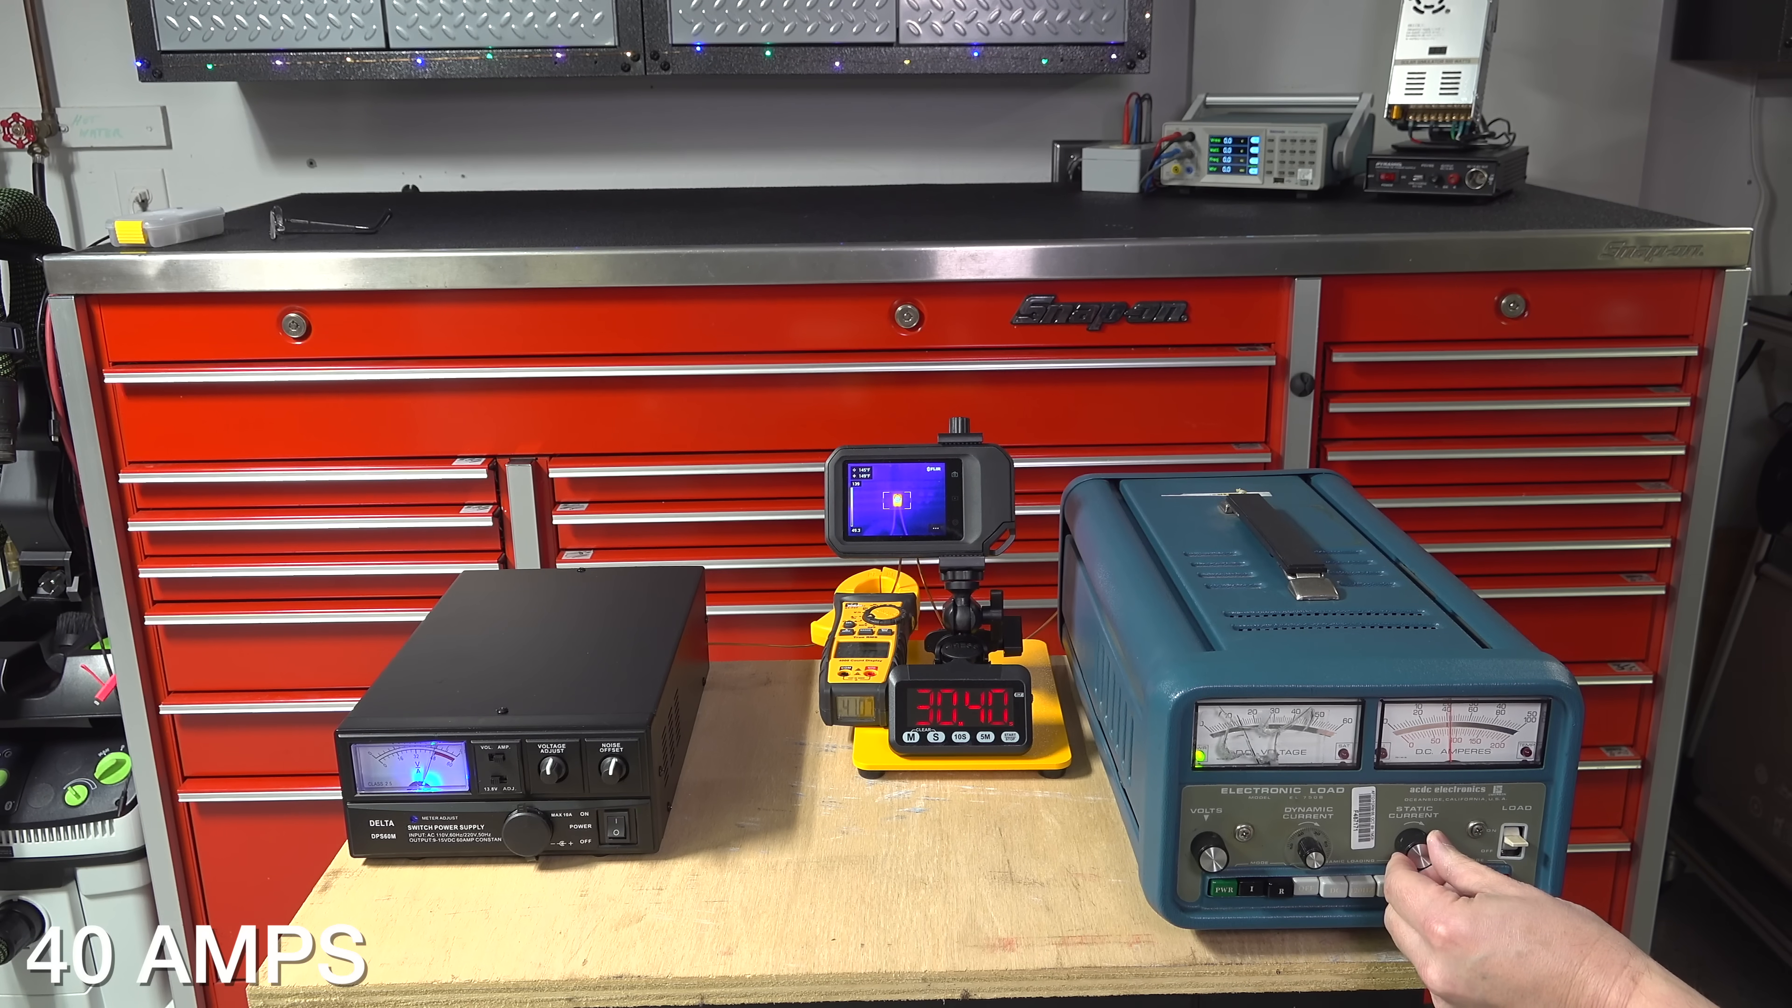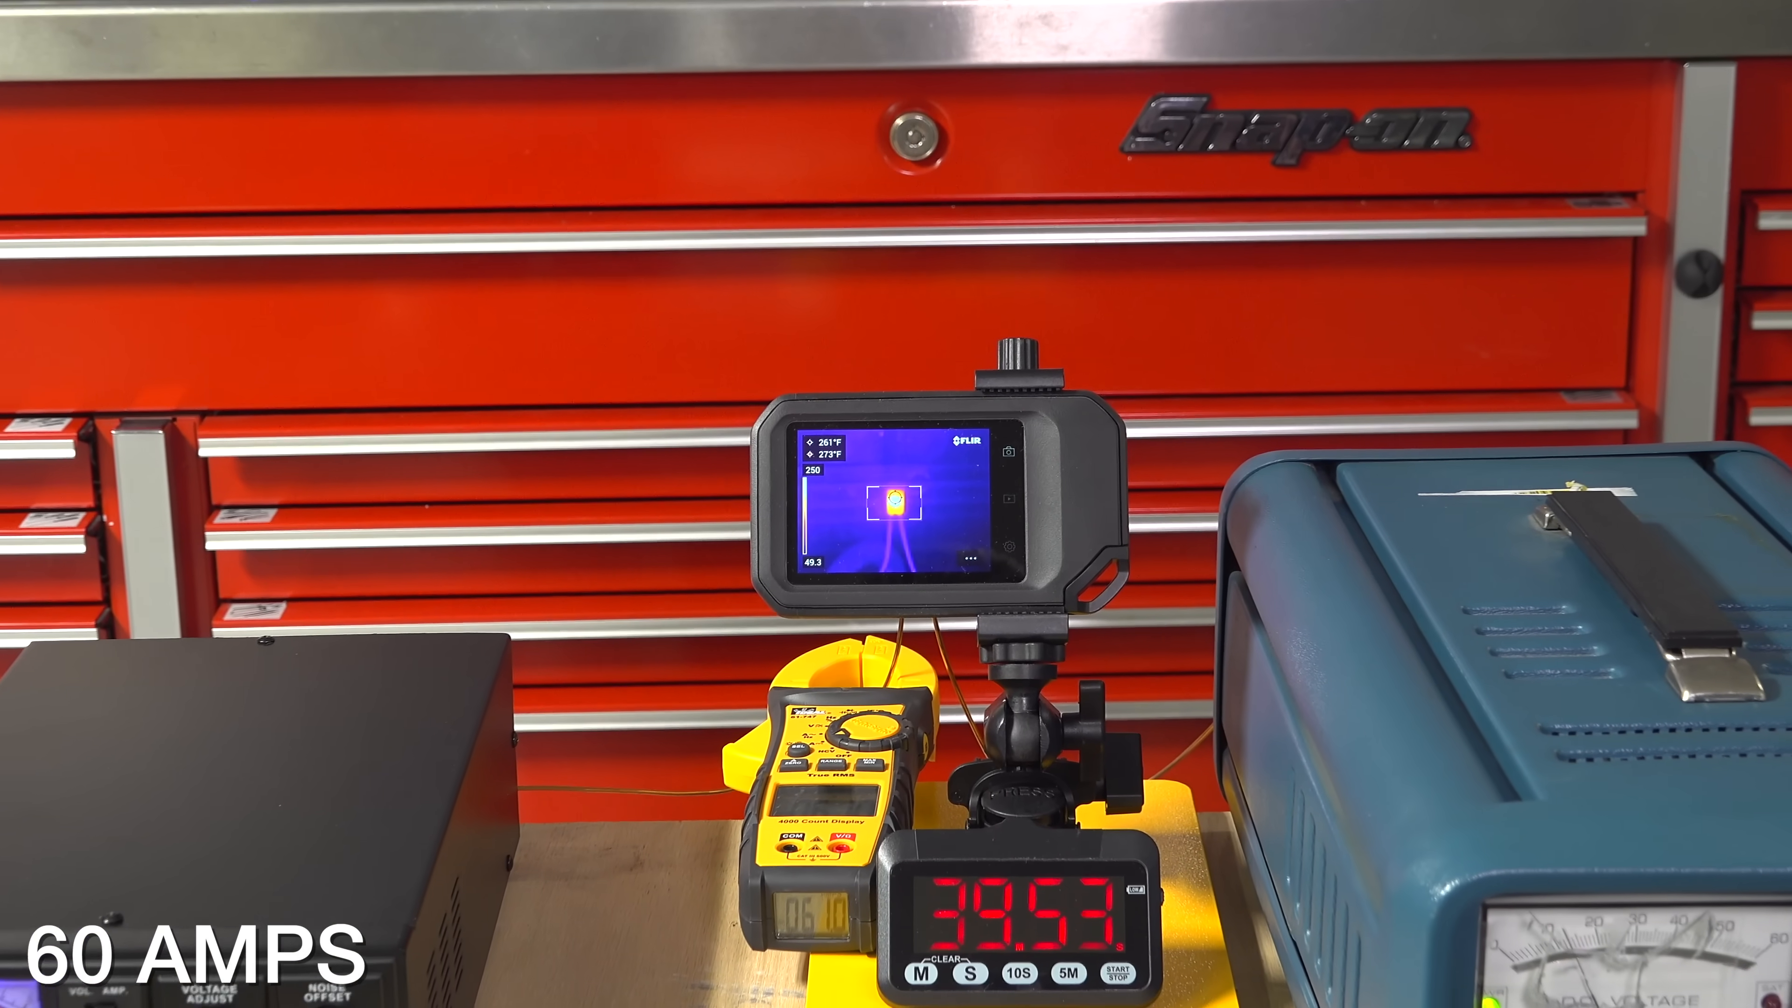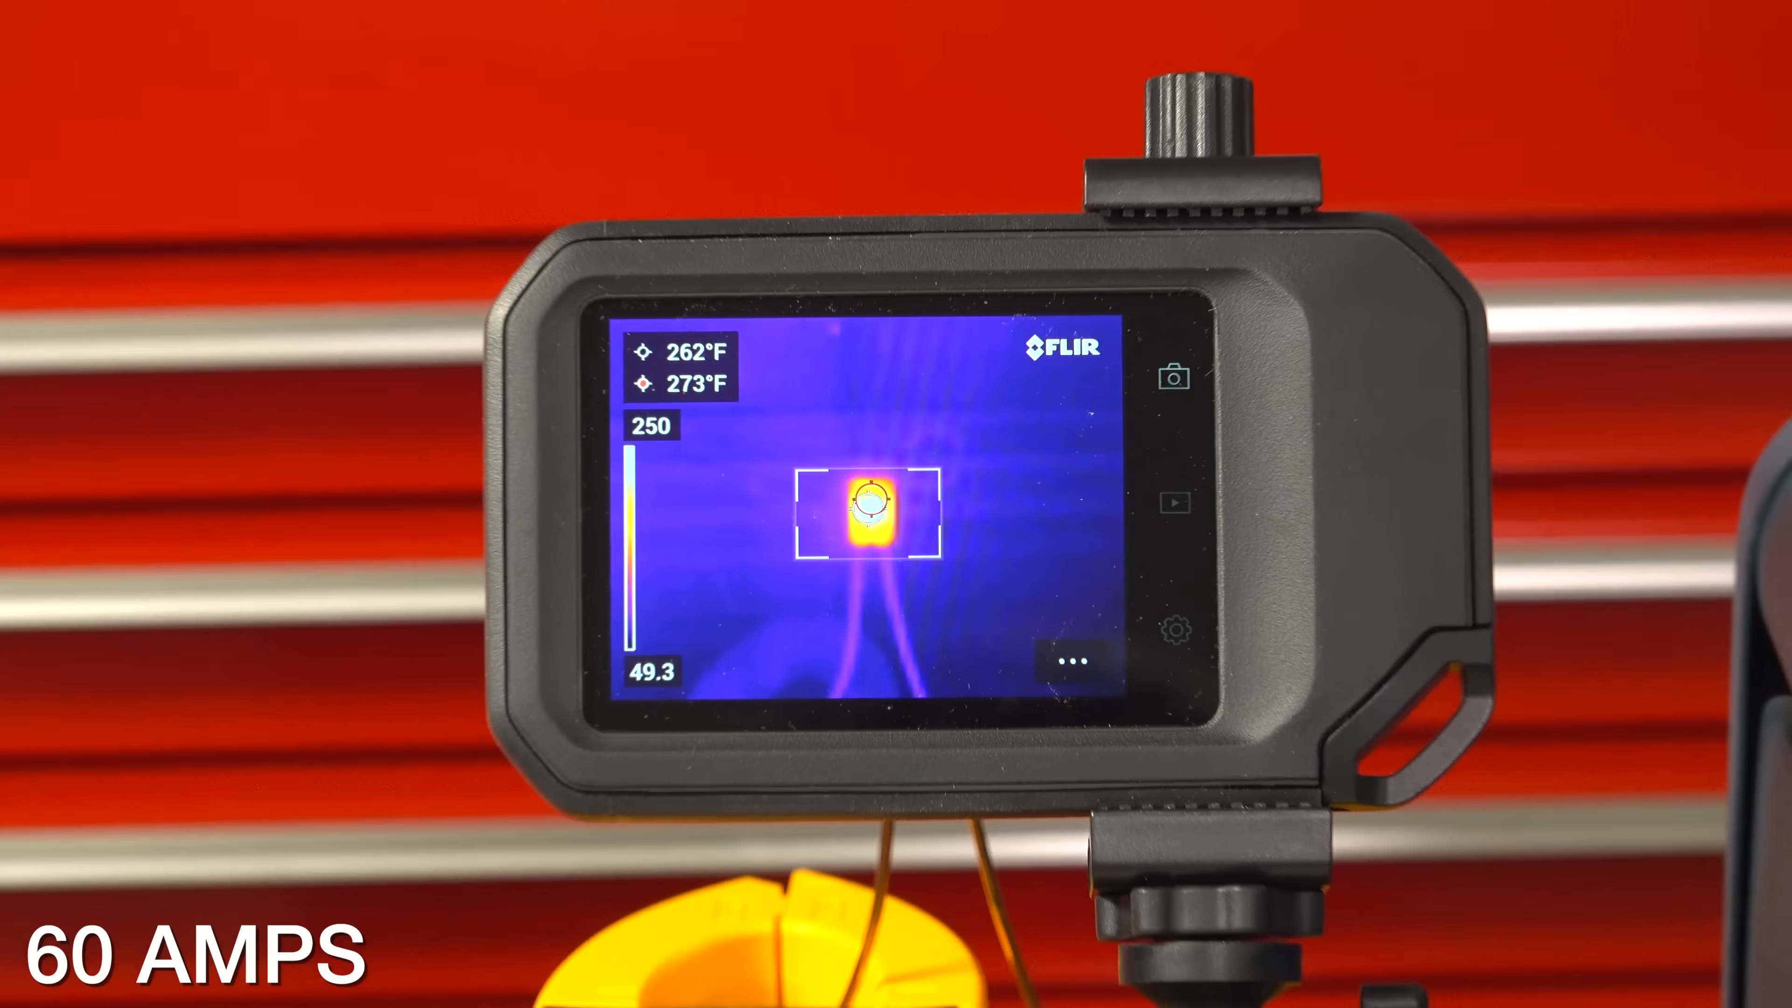Now we're going to do the final test and increase our amperage to 60 amps. Now old houses used to have 100 amps for the entire house. So 60 amps is a lot of power and this is the maximum amount I can do with this setup. After 10 minutes, this was the result at 60 amps. Our connector had reached 273 degrees which is definitely hot but we're at three times the rated capacity.